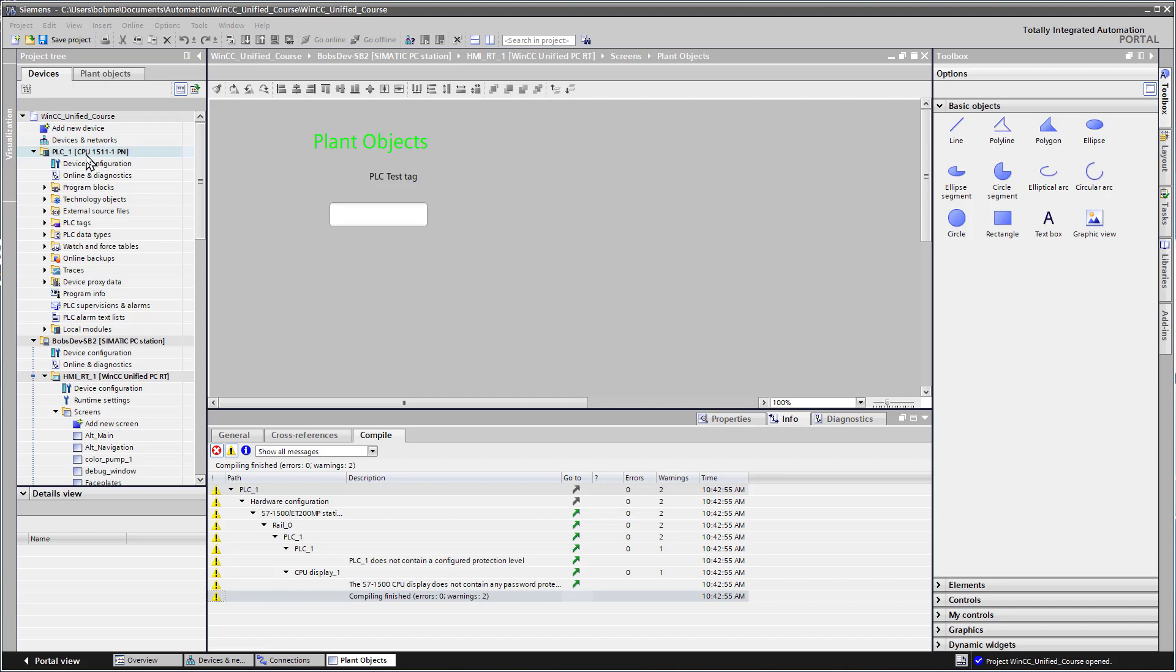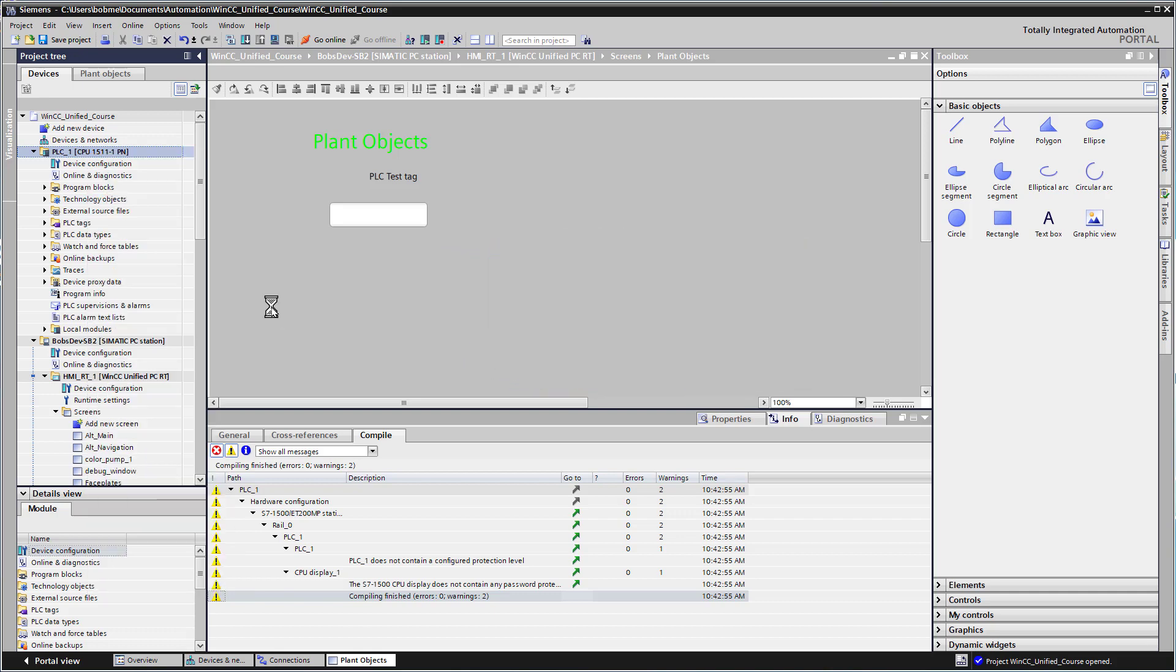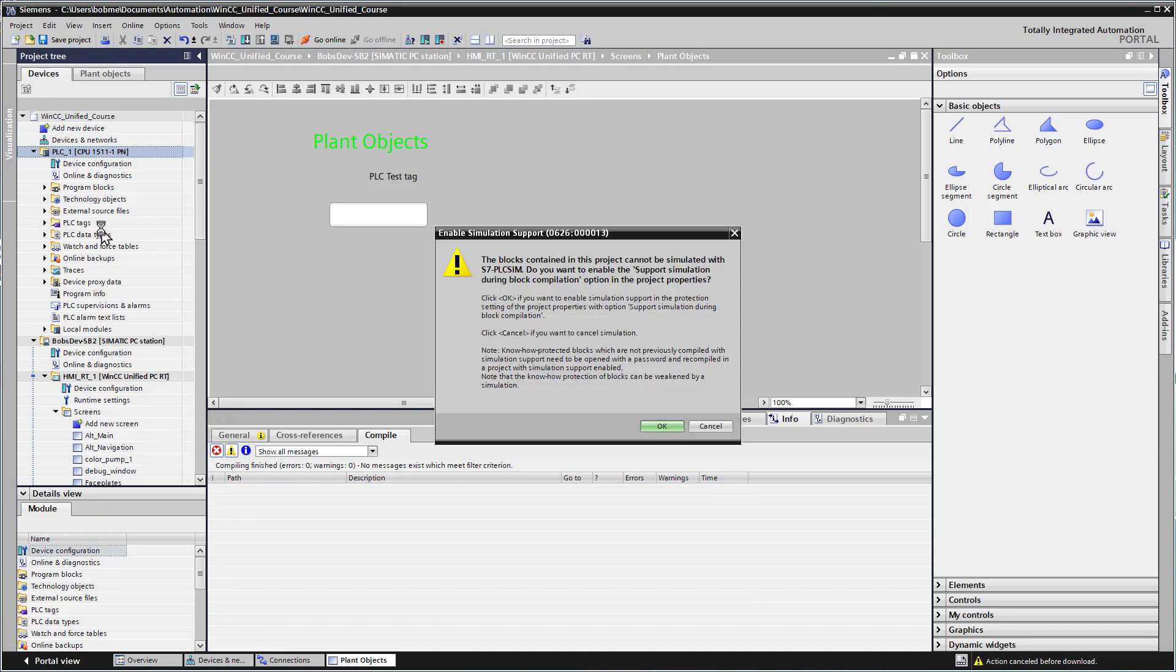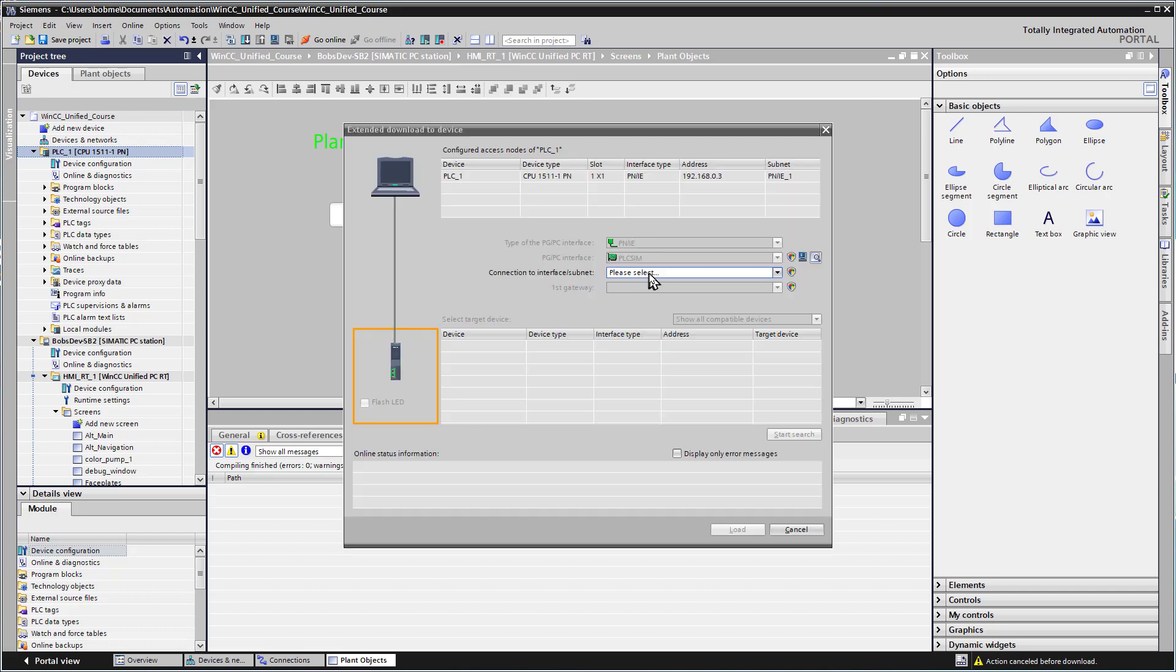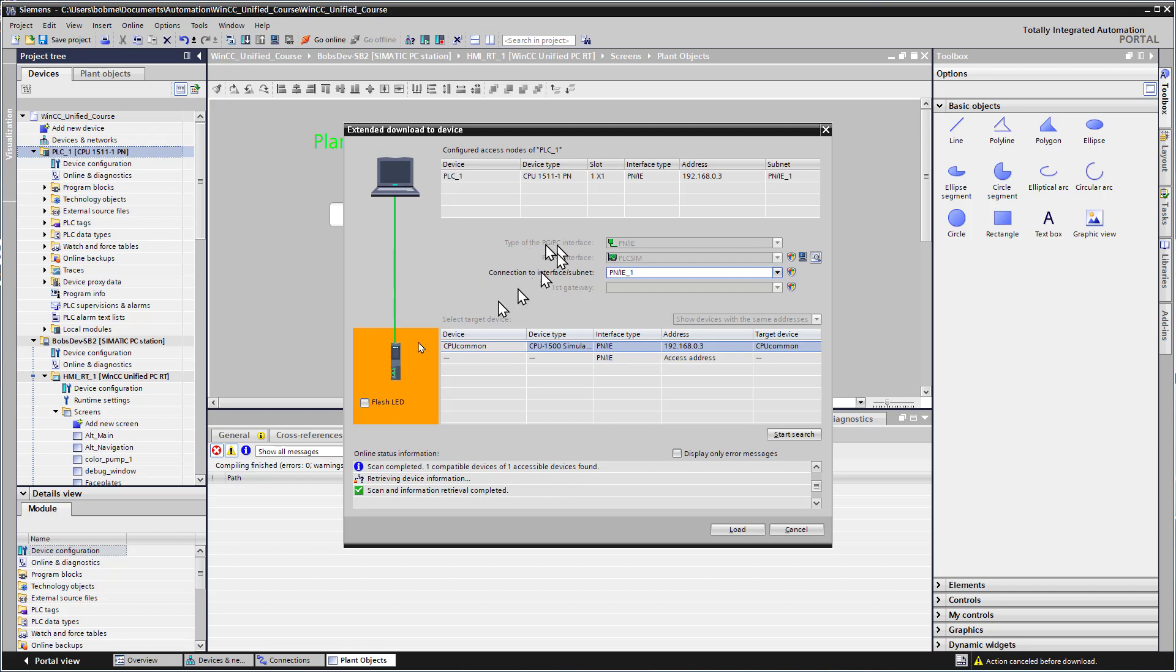Now what we need to do is compile our hardware and software on our PLC. I'm going to right click and do a compile hardware and software. Now we'll want to start the simulation on this PLC. The first time it does, it's going to tell you you need to enable the support simulation during block compilation. We can click OK, then choose PN/IE and do a search. It's going to find our CPU 1500 simulation at .3.